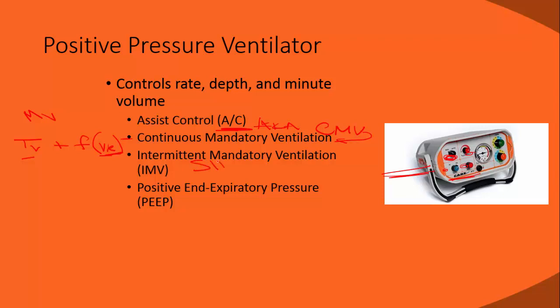There used to be SIMV as a term, for synchronized, but that's gone away because intermittent mandatory ventilation is synchronized. What you'll set here is rate and volume, but when the patient takes a breath, it's going to measure the inspiration. So the inspiration here helps control the ventilation. If they're set to take 16 breaths per minute and they take a breath that wasn't initiated by the ventilator, that becomes one of the 16 and it gives the total volume that was set. So pressure support is something that we would probably have set up.